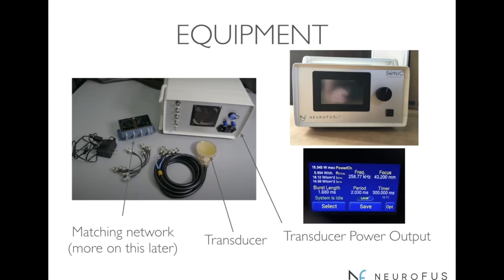Sorry, Rory. So on the equipment side, for the NeuroFUS Pro system, it's actually very straightforward in terms of the components it has. You've got your transducer, which is the speaker I mentioned earlier, and a matching network, which I'll talk about more later. That matching network enables you to move the focus closer or further away from the transducer face, or rather the point where the ultrasound enters the head. The NeuroFUS system also has a touch screen that enables you to configure the parameters you're interested in.